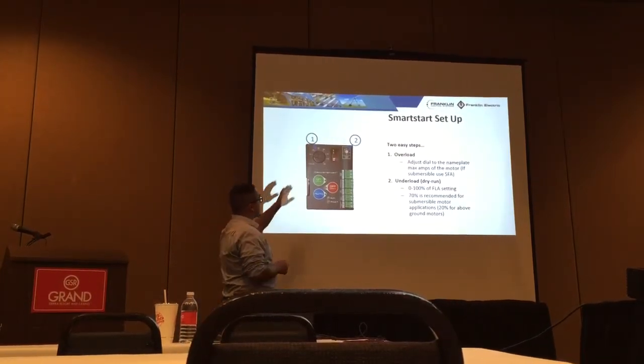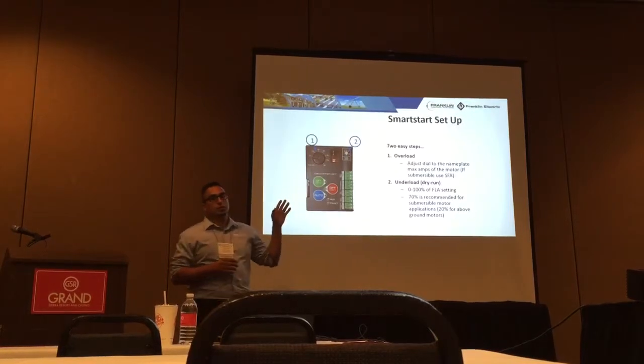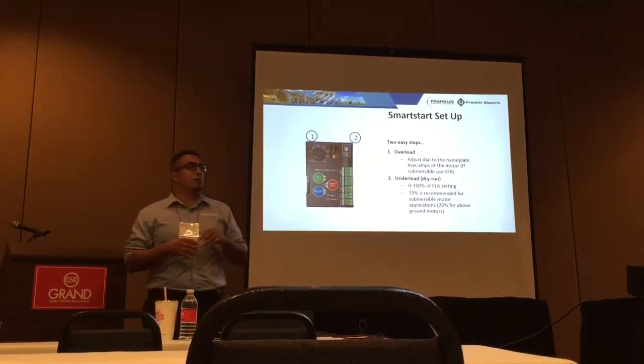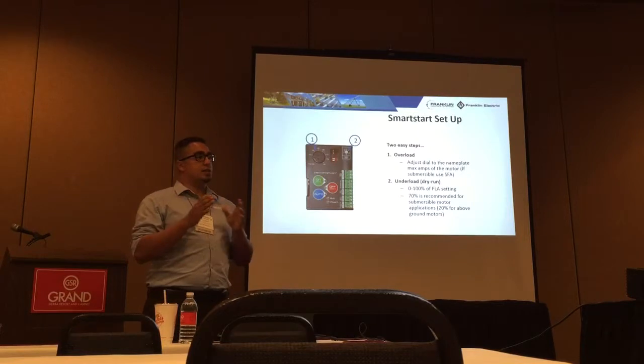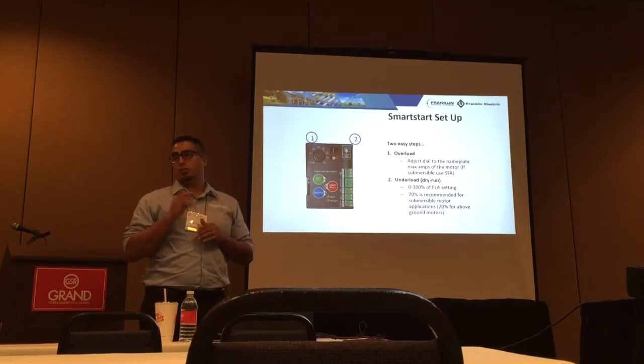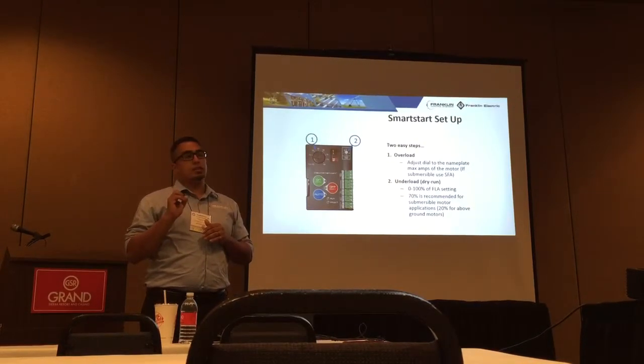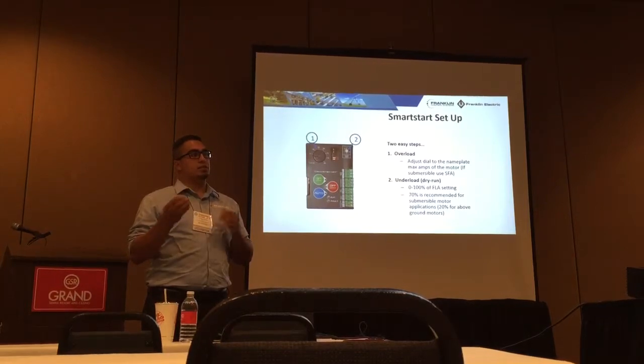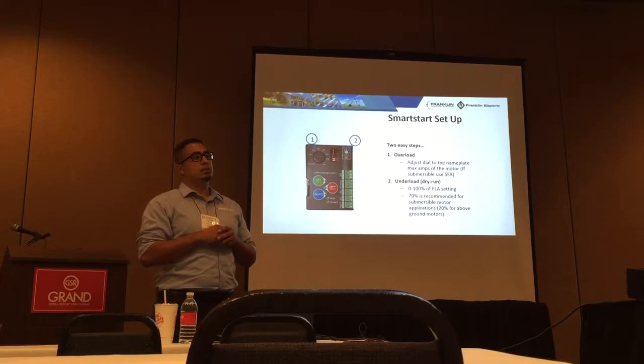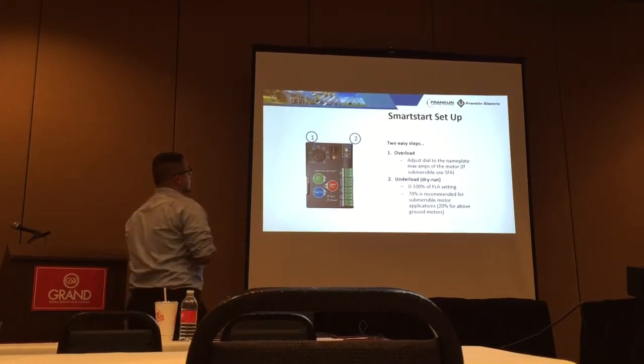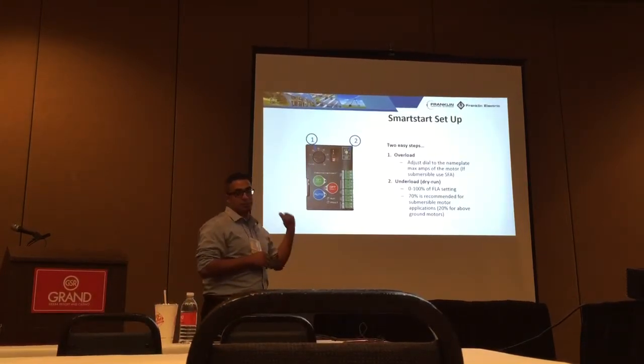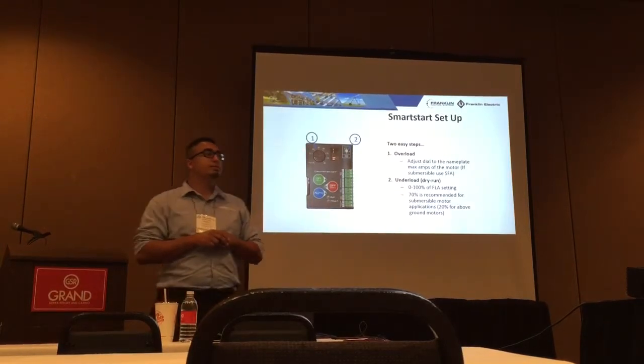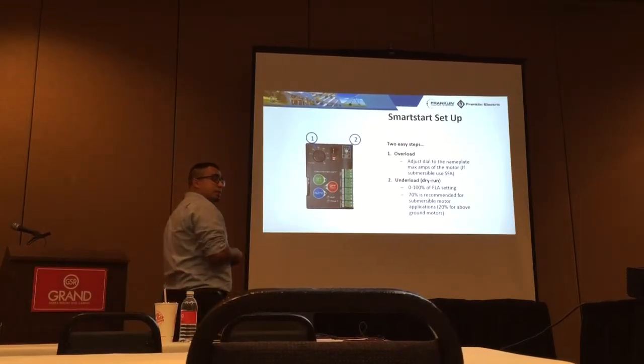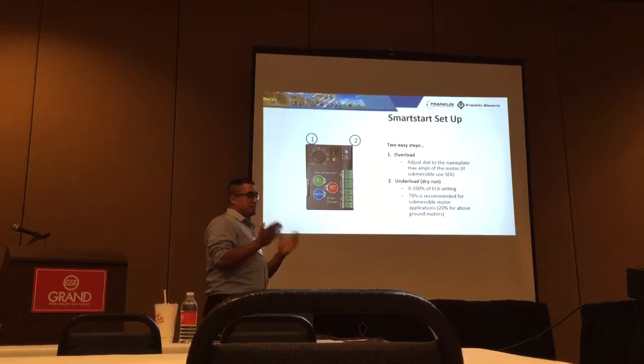So back to your question, in terms of setting it, as soon as you set the service factor amps on the overload, there's a built-in range of about 400 to 800% that it's looking for an inrush capture. So when it looks at that inrush capture, it compares it to what the amperage has been set on the dial. I have a question. Are you supposed to set that dial to the full load amps and not the service factor? Service. The label, this picture's old. It's service. Okay, so the new panels are going to be service factor? Yeah. Because some of the older panels are the FLA. They're a mix, yeah.